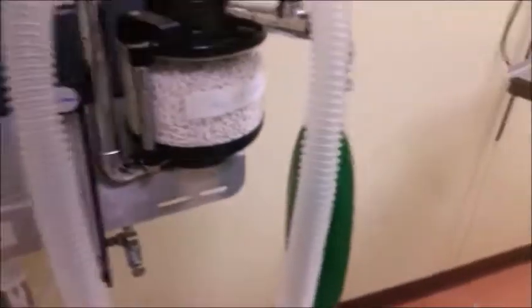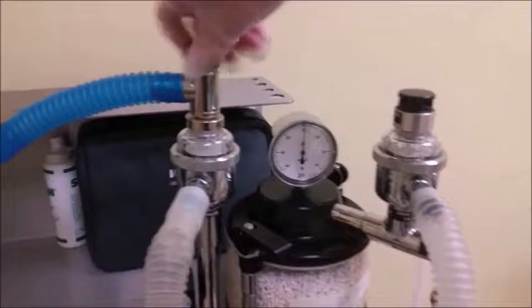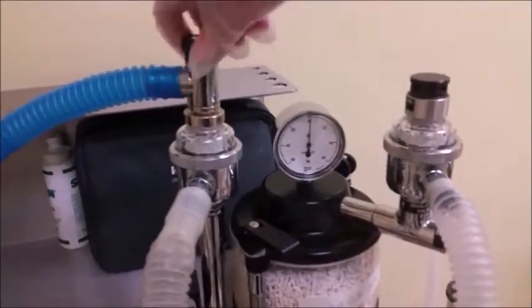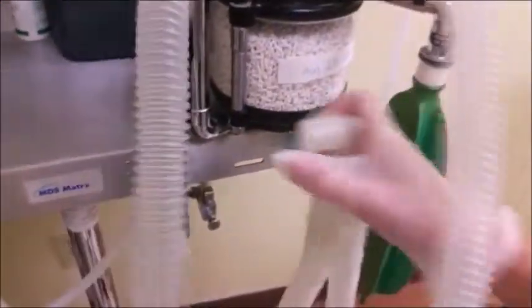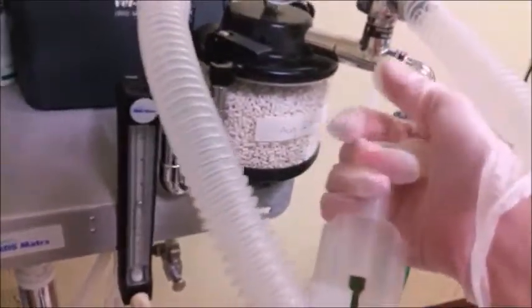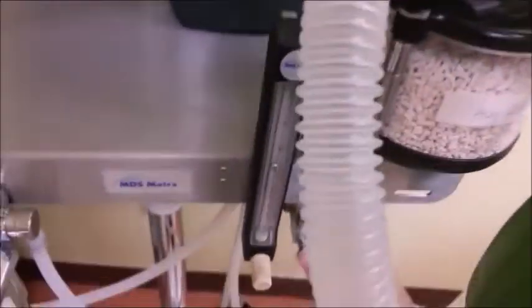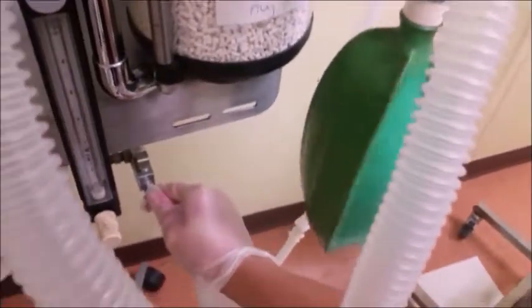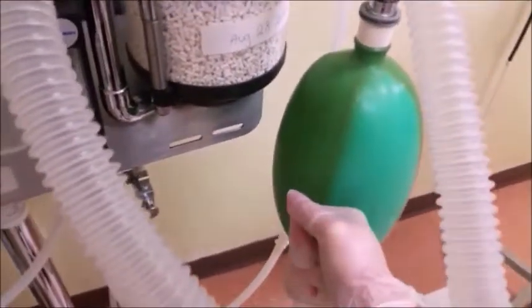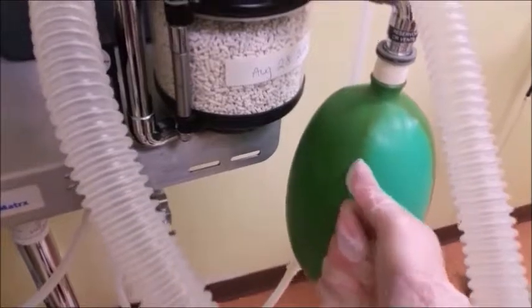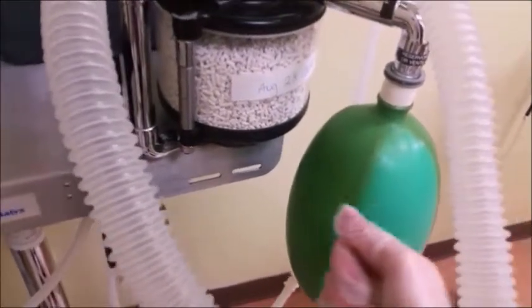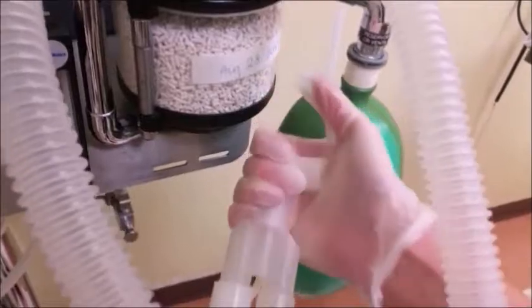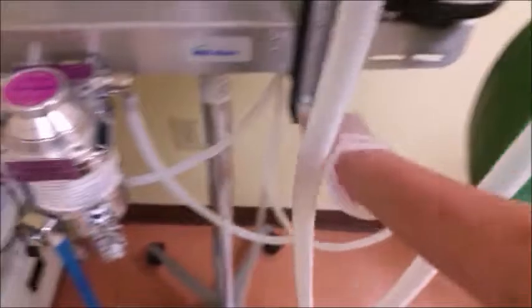If we are doing a leak test, our pop-off valve is going to be closed. I am going to hold on to the end of my Y-piece tubing, capping that off, and I can flush oxygen through our system, and a positive test should show that our reservoir bag is holding the full amount of gas and that it is not seeping out until I release that pressure. So that is a positive test. We have no leaks in our system.